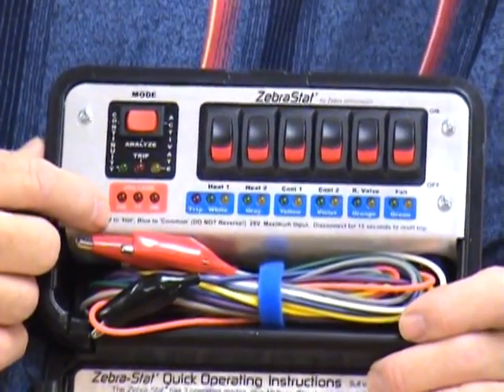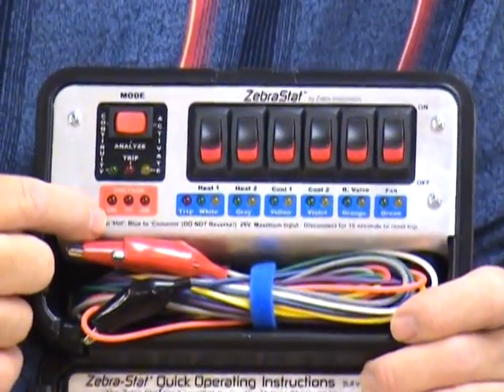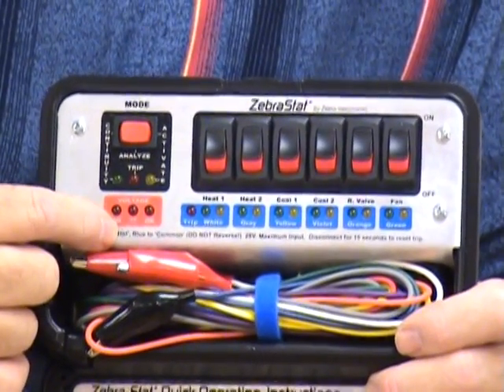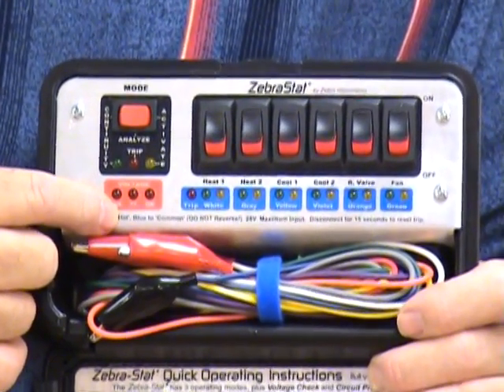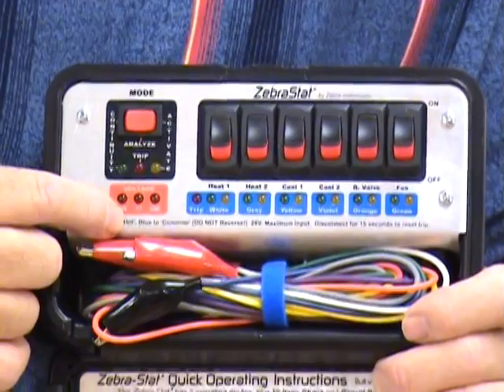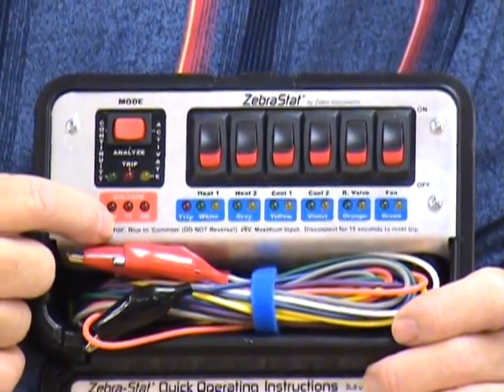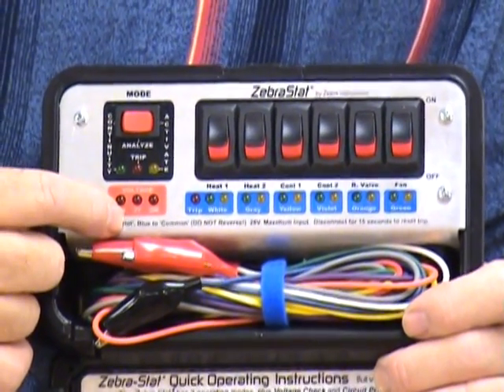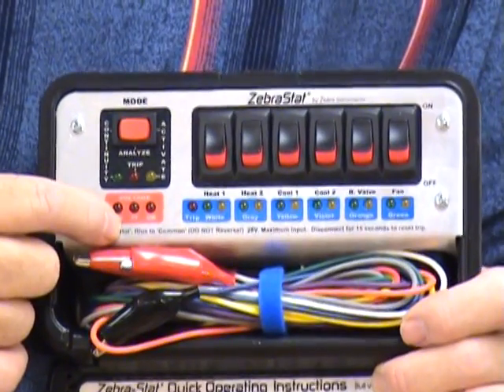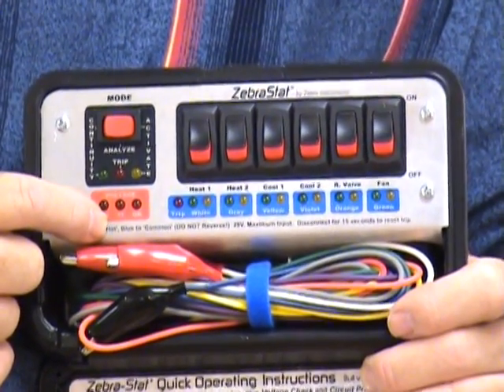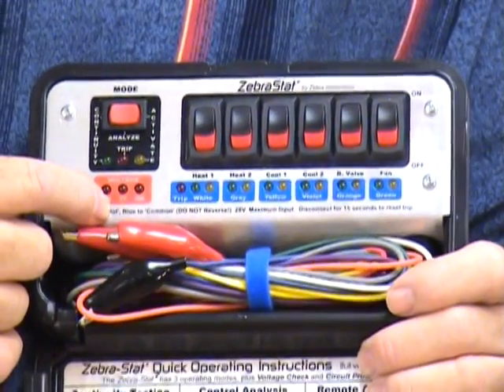The fourth feature that the ZebraStat does is it automatically monitors voltages with these lights. If all 3 red lights are on, you've got great voltage coming from your transformer. But if you ever notice that 1 or 2 of these lights are out, it says that you've got questionable or not enough voltage to pull in a contactor, for instance, on your outdoor unit.